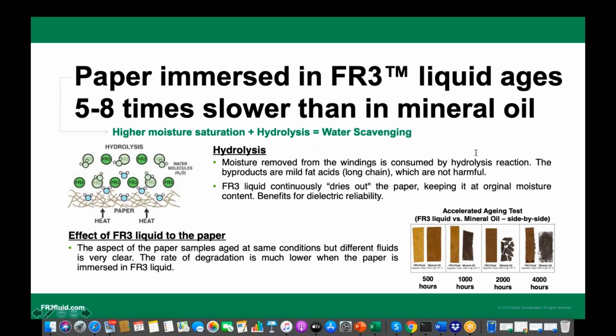What happens when you impregnate this conventional kraft paper with this fluid? It keeps it continuously dry and enhances its life, because when you keep it dry, or required dry, I would say, not completely dry, it increases the life of paper by as high as 5 times in the case of kraft paper and as high as 8 times in the case of thermally upgraded kraft paper. You will find a lot of published data, be it Stuttgart University, Manchester University, UL Laboratory, FM Global, a lot of US IEEE data. Everywhere you'll find similar equations, and it's well proven that paper impregnated with ester fluid, specifically natural ester, brings a huge life in the insulation. And there is some hydrolysis which we'll discuss later. Let's move on. Next slide, please.